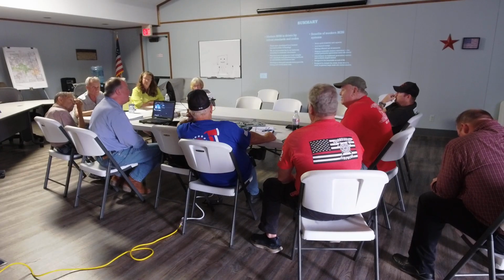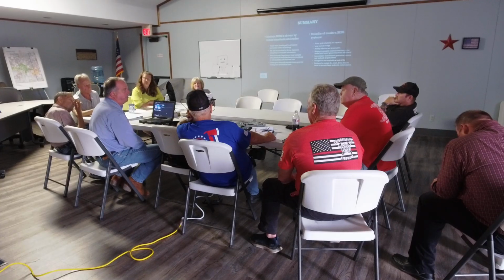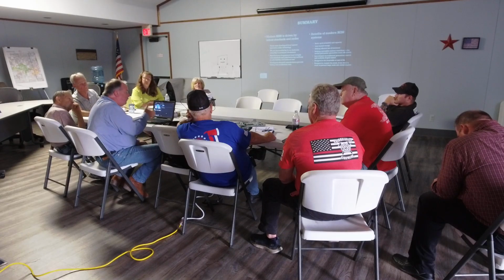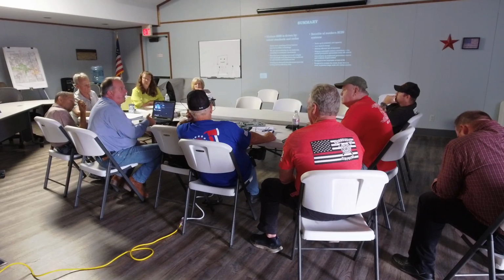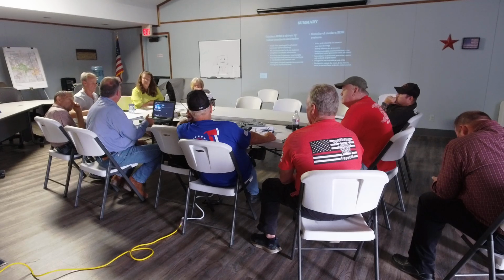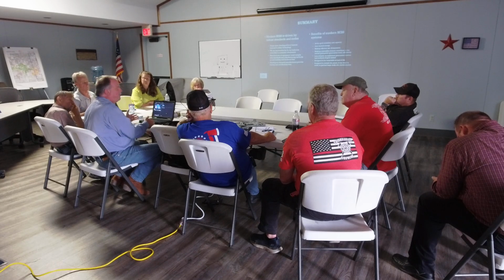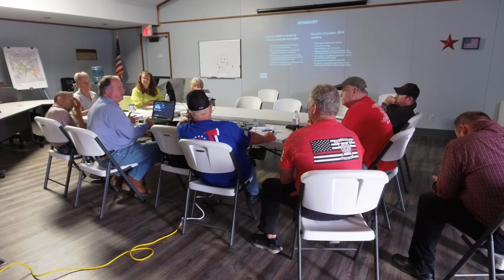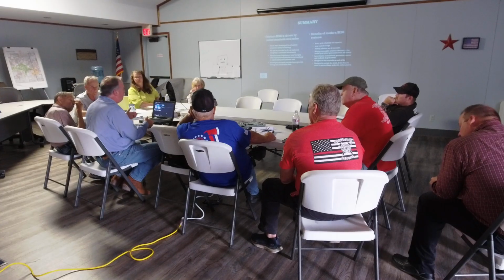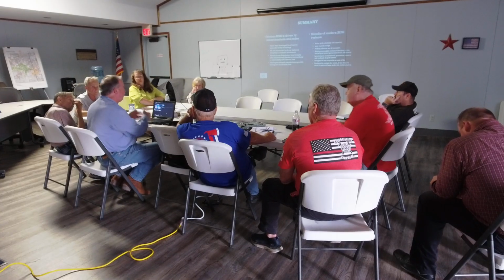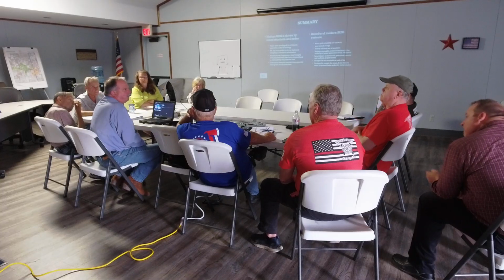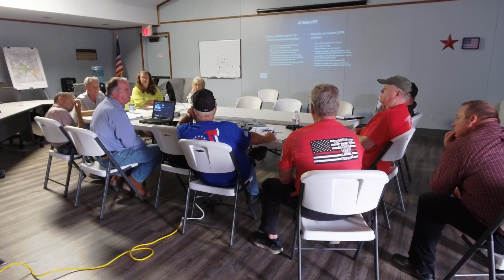But a lot of good came out of that, because those batteries were very early into UL 9540 and had gone through testing, so the fire service knew exactly what to expect. The challenge comes when an overriding standard requires us to have a sprinkler system, when we'd rather not have water flooding onto batteries. So NFPA 1 kind of gets in the way, and that's why everything's being moved outdoors. We don't have that requirement, and we don't have that issue.